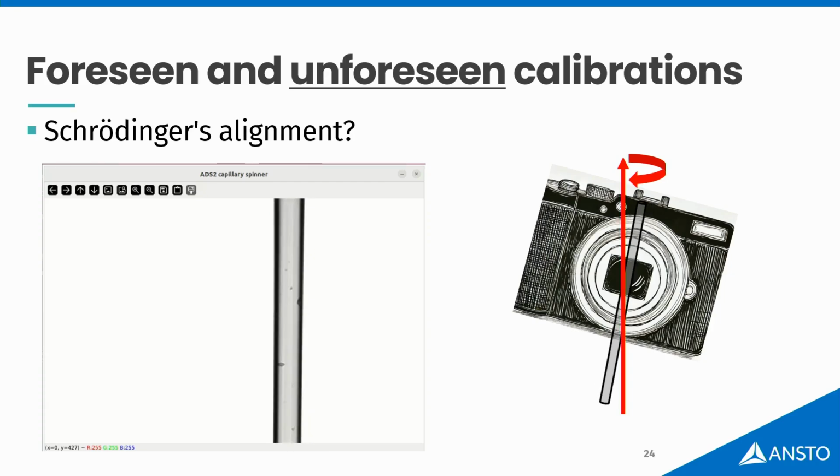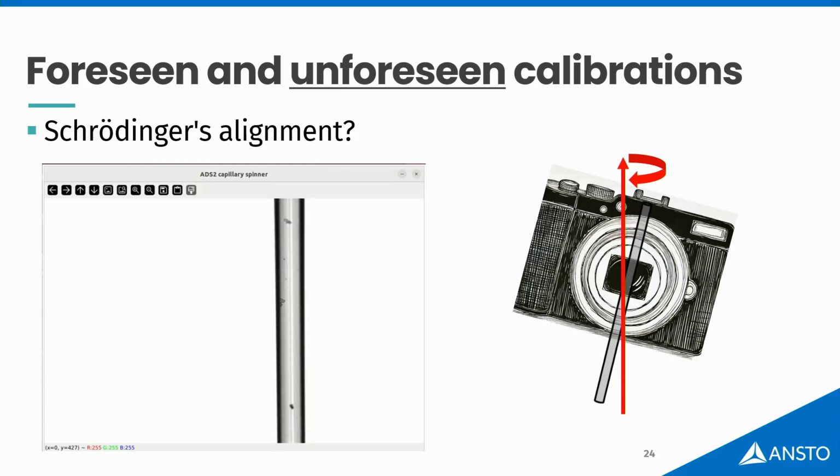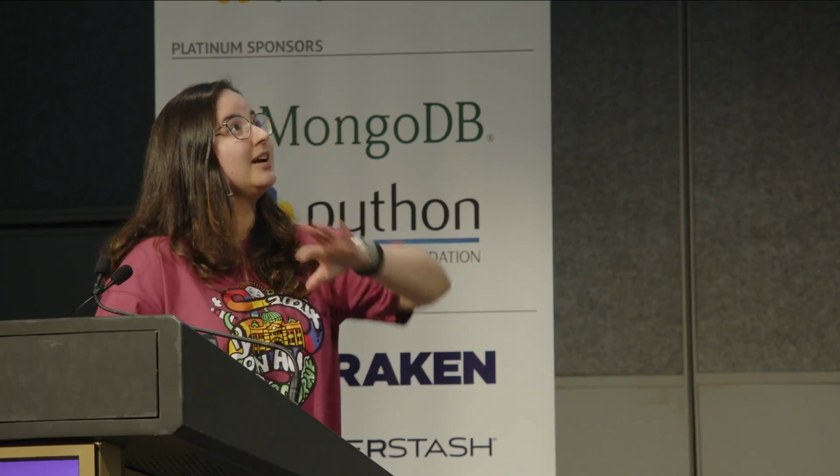Look at this. Tell me if that's not what's happening. The camera is placed manually on the stage. And it's very well placed, because this crookedness that I found was like 0.8 of a degree. It's very good for manual placing, but it was not 0. So of course, we would see a difference in a capillary that's 1 millimeter thin. Fortunately, I was able to fix that, and I was able to factor that into the code. And we can align the capillary now.